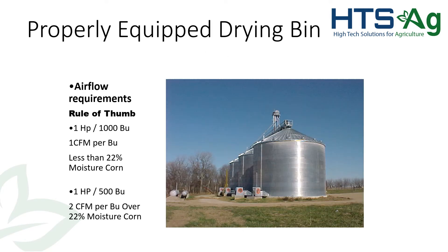Airflow is another key element. General rules of thumb: one horsepower per 1,000 bushels gives 1 CFM per bushel, which works for corn under 22% moisture. One horsepower per 500 bushels gives 2 CFM, which works for corn over 22% — though most bins probably don't have that. More likely you'll have one horsepower per 2,000 bushels at 0.5 CFM or less, even down to 0.25 CFM. At 0.25 CFM, we're not really going to be able to do much drying — we'll really only be able to change the temperature of the grain.